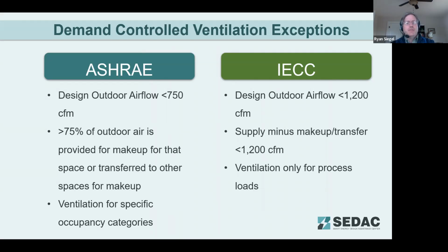And IECC phrases that a little bit differently, looking at the differential between the supply and the transfer air being under 1200 CFM and process loads being directly excluded. For ASHRAE, it gets into the occupancy categories rather than the specific uses.